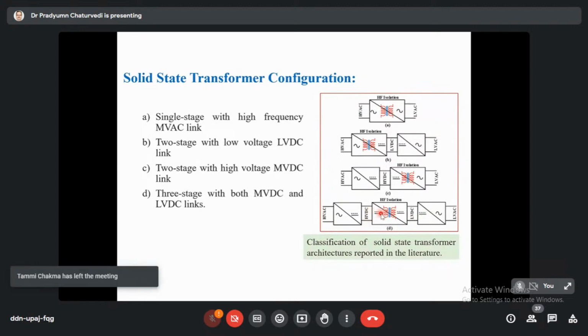So DC to AC: this will contain one inverter at the front end, and again one converter at the back end. So this will be having AC-DC, DC-DC, and DC-AC stages. This three stage SST is most commonly used, because you can see from this figure that you will have two DC buses, one at one voltage level and second at another voltage level. Nowadays you cannot predict EV charging, how many batteries are to be integrated in the next 1, 2, 3, or 4 hours.